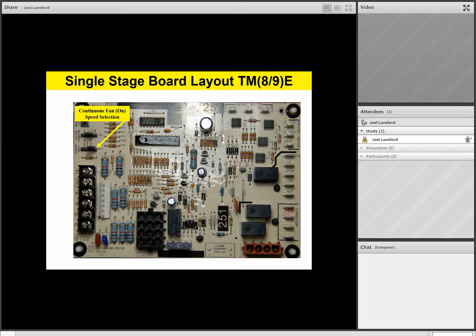So this gives us some nice options to allow a continuous fan operation, because a lot of times homeowners like to run the fan all the time, but they don't want it running on full cooling speed or high speed. So this jumper allows a continuous fan on speed selection other than just high speed cooling.